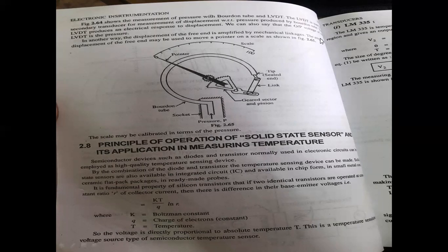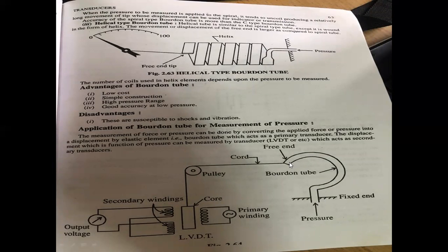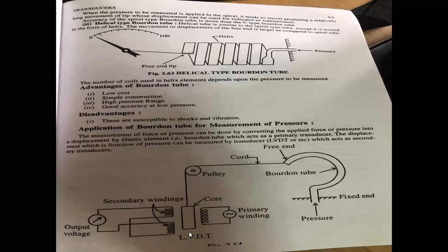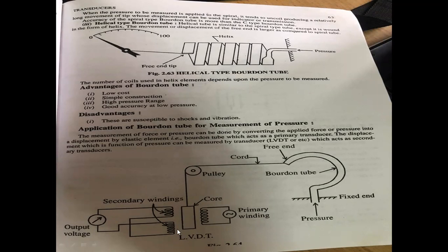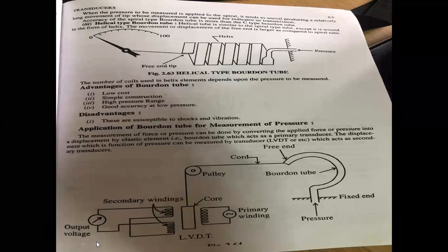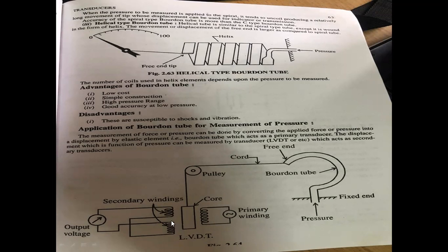When pressure is applied, the free end changes its position and length. The movement goes through the iron core of the LVDT — the core moves either upward or downward. As the iron core is displaced, it disturbs the magnetic field. We keep the core in the center so both secondary windings give equal output voltage, and displacement causes a voltage difference.